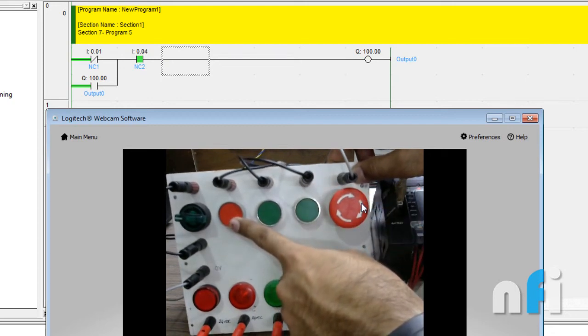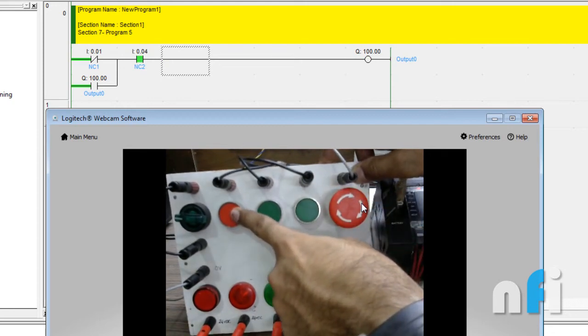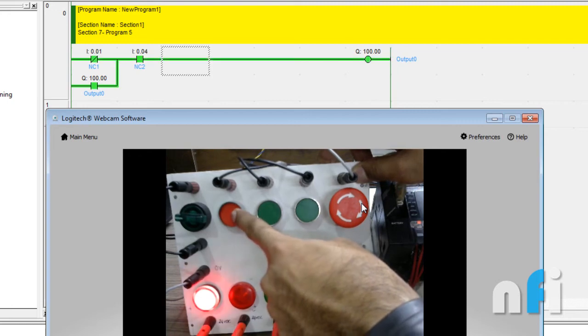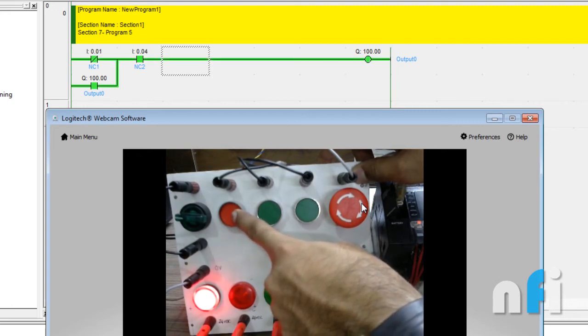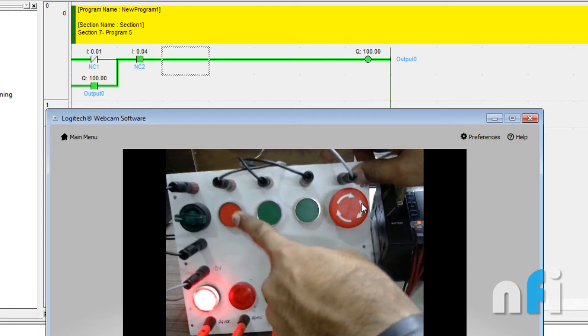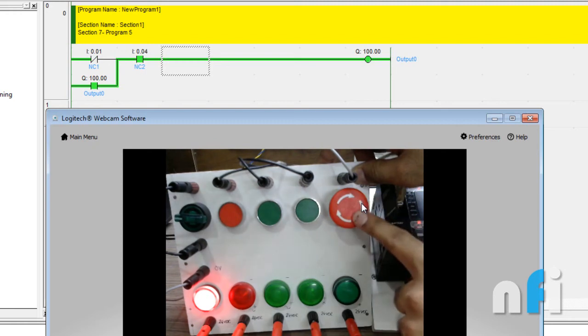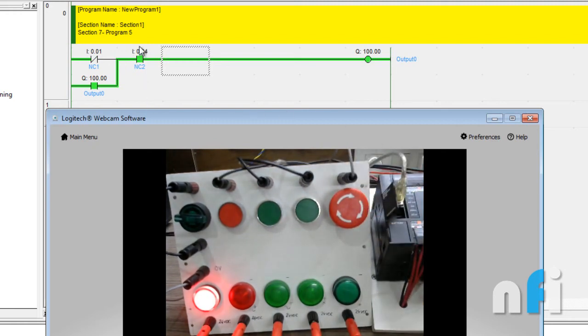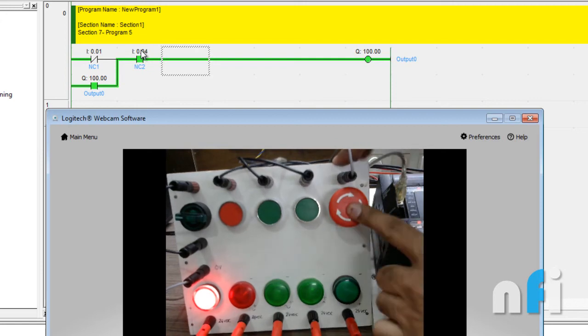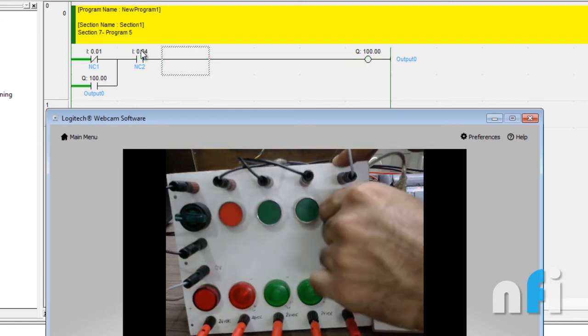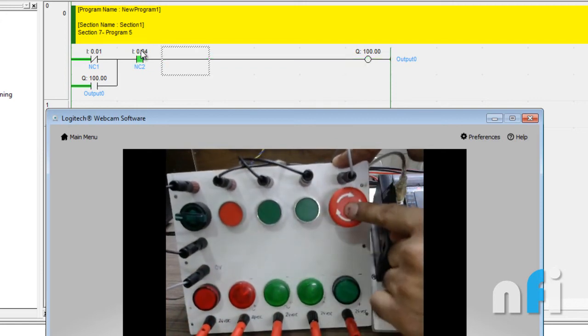This will be used to unlatch the output because this is an NC contact in the PLC. When I press this one, it will give a pulse and latch the output like this. In this situation, output is latched. If I release, output is latched. And if I press this one, the NC contact which is over here will be open and it will unlatch the output.